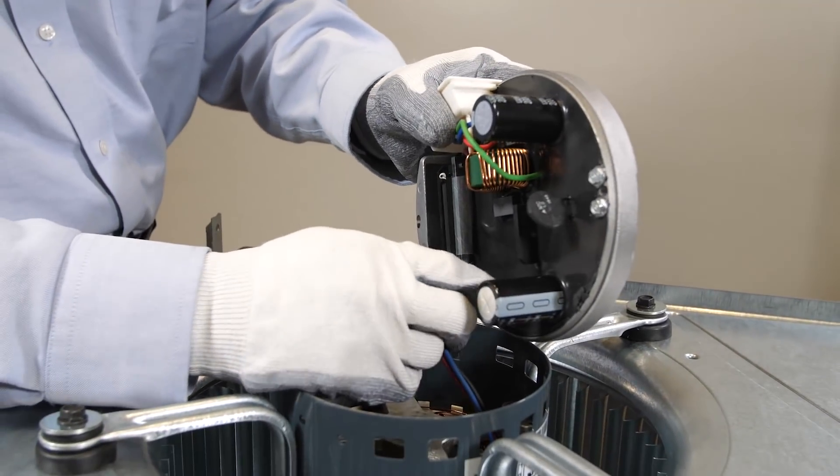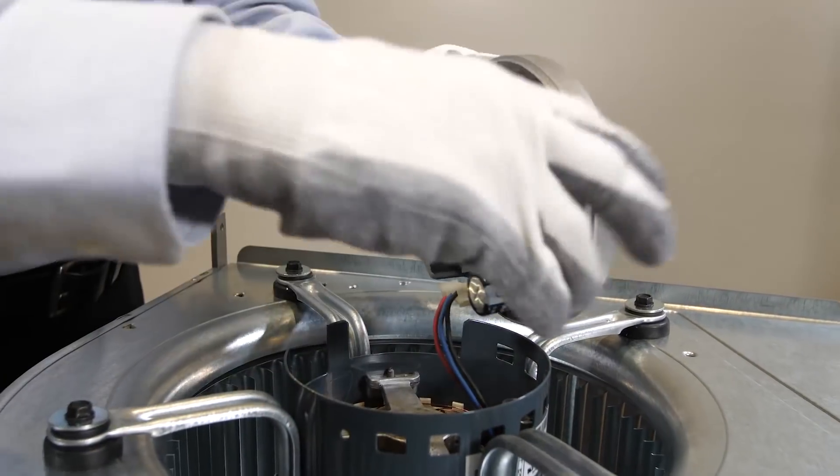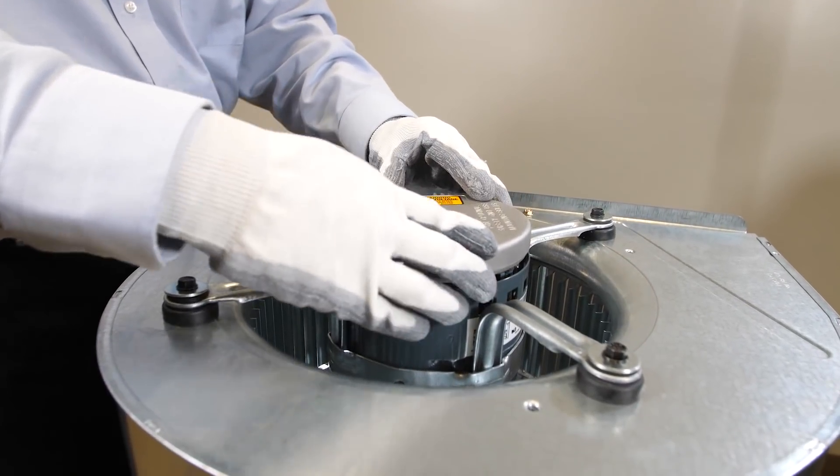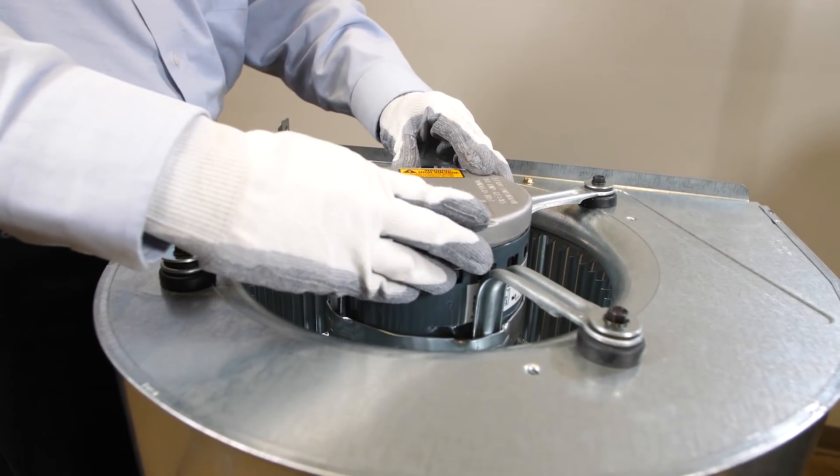Once you have the proper replacement module, connect the three wire plug. Make sure the connector is fully seated and latched and align the power connector and aluminum heatsink with the notches on the motor housing.